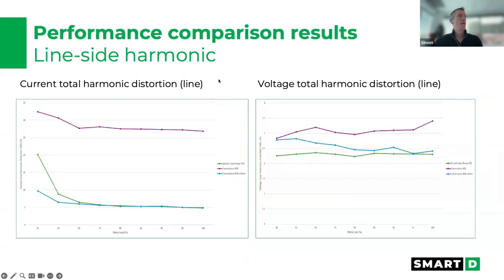In terms of harmonics results, you can see the high harmonic content from your standard 6-pulse without filtering. And you can see that both the passive harmonic filter and the clean power VFD get below 5% harmonics at full load. Now, as I mentioned, this is a test in a lab with a very stiff grid. So in your typical environment, you actually might get below 3% harmonics at full load. You can also see the result in terms of voltage total harmonic distortion. This is the harmonic distortion that the utility is interested in because that's what is polluting beyond your grid. And you can see here that the clean power VFD in green outperforms both the standard drive, of course, and even the standard drive with a passive harmonic filter.